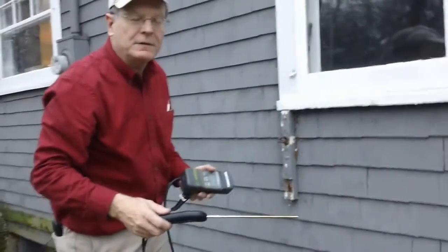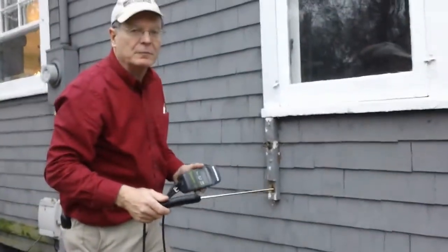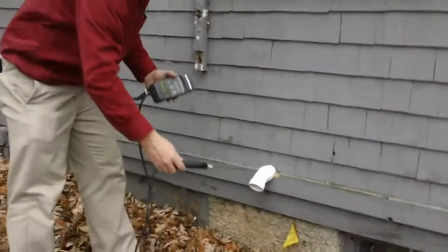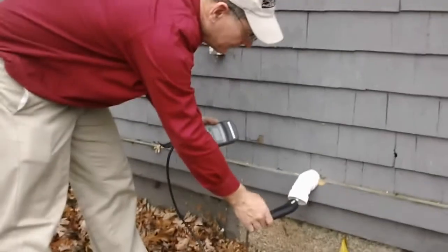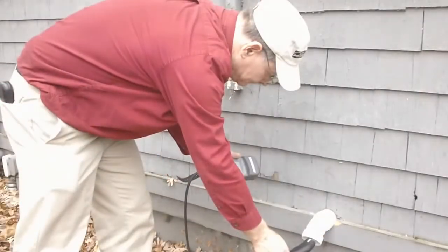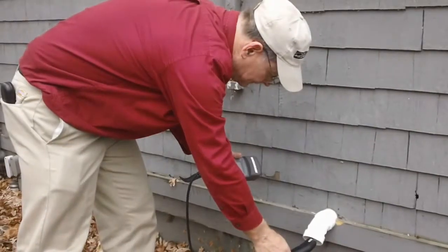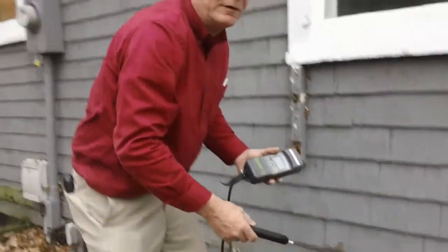This is the combustion safety test for the hot water heater that was replaced. It's a more energy efficient power vent type. We're checking the carbon monoxide level with our tester here. And we have a very safe level, and it passes our test on our post-inspection.